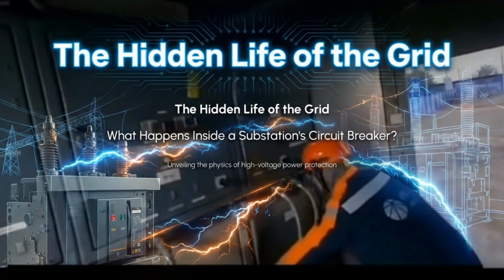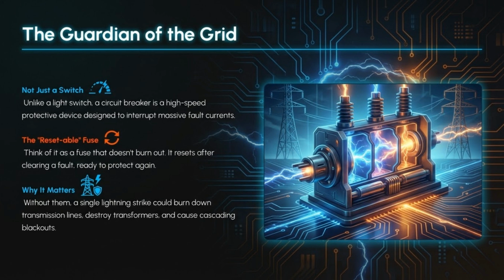Welcome to the hidden life of the grid. We will be unveiling the physics of high-voltage power protection by exploring what happens inside a substation's circuit breaker. The circuit breaker is the guardian of the grid. Unlike a simple switch, it's a high-speed protective device designed to interrupt massive fault currents. Think of it as a resettable fuse that stands ready to protect the grid from catastrophic events like lightning strikes.